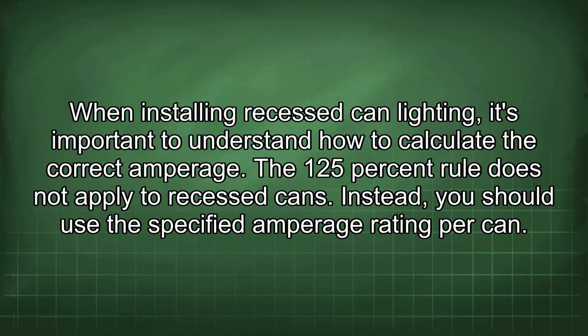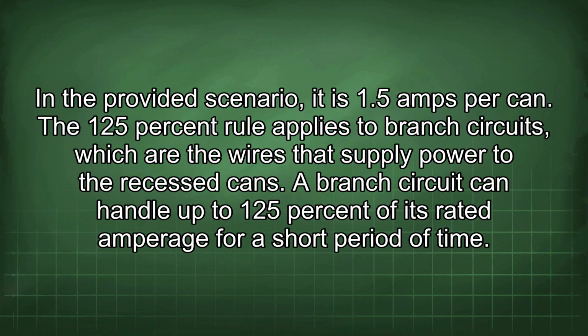When installing recessed can lighting, it's important to understand how to calculate the correct amperage. The 125% rule does not apply to recessed cans. Instead, you should use the specified amperage rating per can. In the provided scenario, it is 1.5 amps per can.